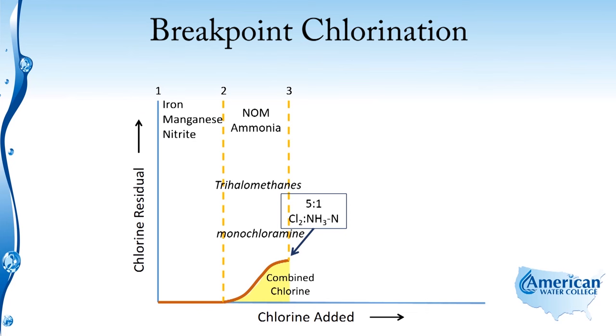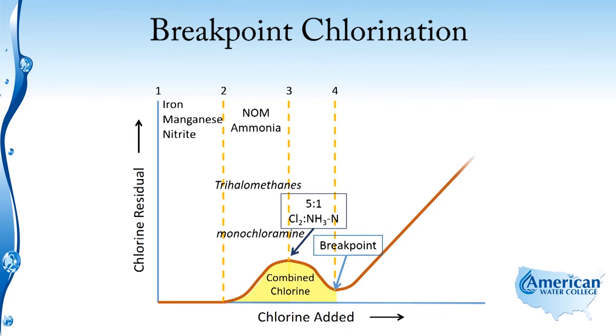As we continue adding chlorine, there's a reaction between the chlorine and the ammonia and nitrogen, and it starts destroying that residual until it bottoms out at point four, which is what we call breakpoint. At the breakpoint, we've reduced the chlorine residual as far as it's going to go. Now as we continue to add chlorine, we're going to see a linear increase in the chlorine residual, and it'll be in the form of free chlorine.